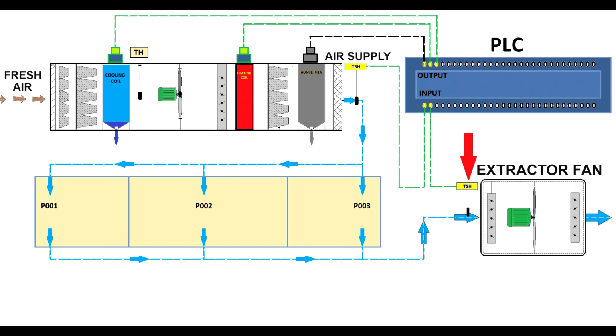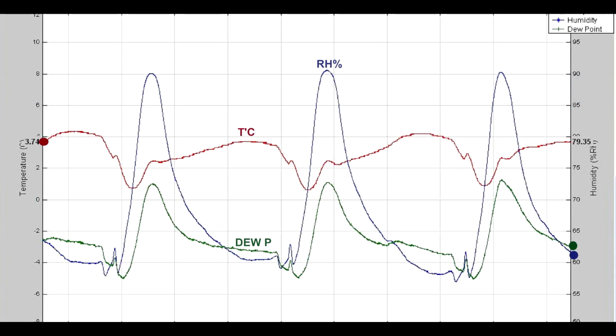The temperature and humidity probe is positioned within the extractor fan duct. This configuration causes a delay in capturing changes in air temperature and humidity. Consequently, the PLC receives instructions from the probe situated in the extractor fan duct, resulting in delayed responses by the actuator. This delay manifests in the temperature and humidity trends as illustrated below. Regrettably, this delay in response can cause temperature and humidity within the clean room to deviate from the desired parameters.